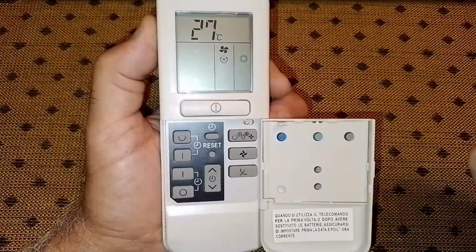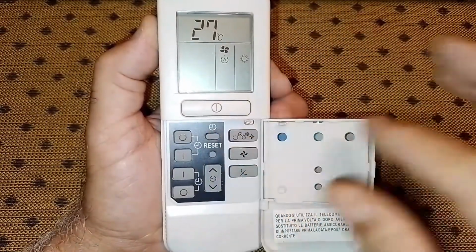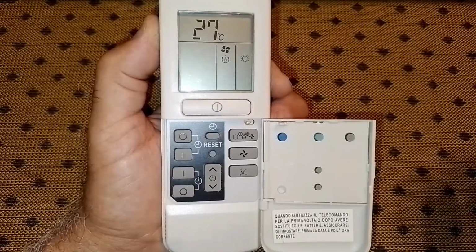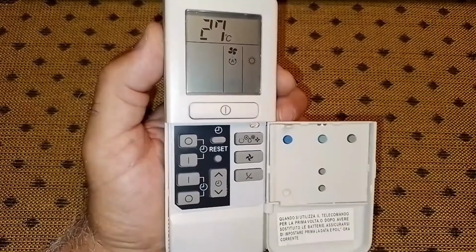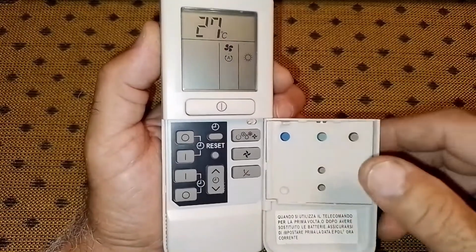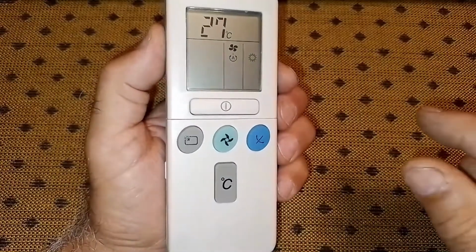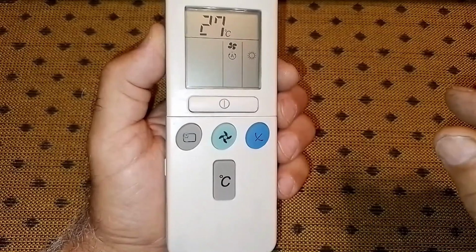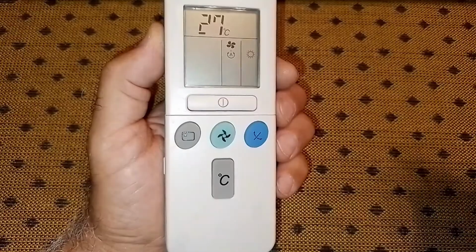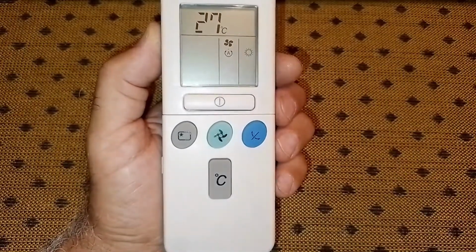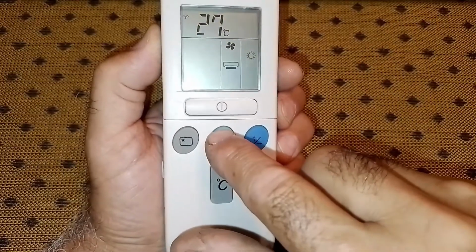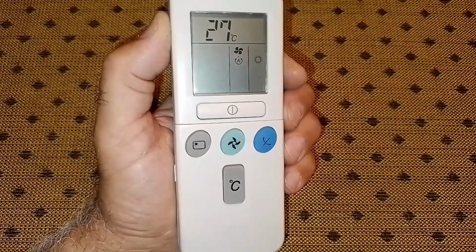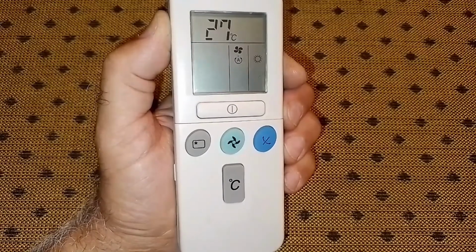In this mode, we set the temperature above 26 degrees. Because hot air accumulates at the top, it will cause the air conditioner to turn off and on more often. We recommend setting the air conditioner fan speed to auto, because in this case the fan speed will be selected by the microprocessor according to the condensation pressure, and the air conditioner will work more efficiently. At the same time, the evaporator will be covered with snow only when the temperature approaches 0 degrees Celsius.